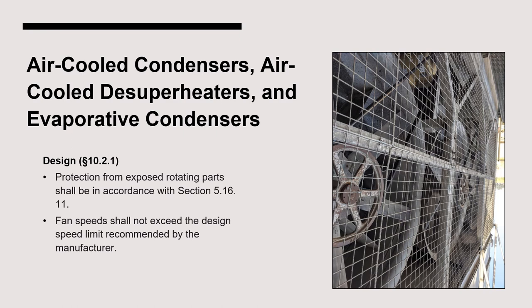The next section of Chapter 10 outlines proper design for air-cooled condensers, desuperheaters, and evaporative condensers. Section 10.2.1 requires that protection from exposed rotating parts be in accordance with Section 5.16.11. As shown in the picture, evaporative condensers are installed with metal grating across the fans as a protective measure. Additionally, fan speeds must not exceed the design speed limit recommended by the manufacturer.